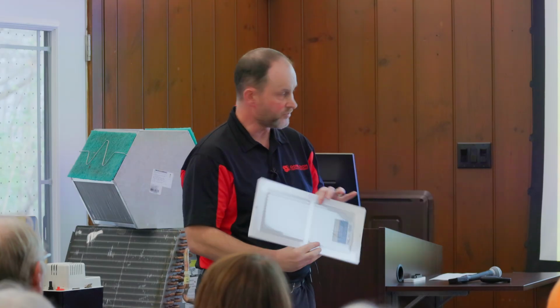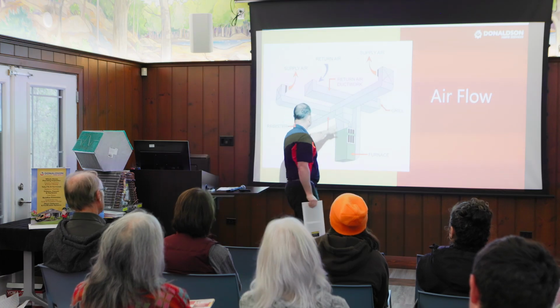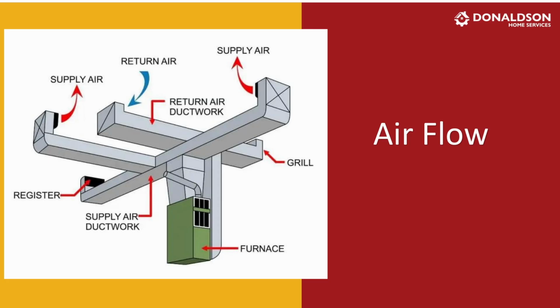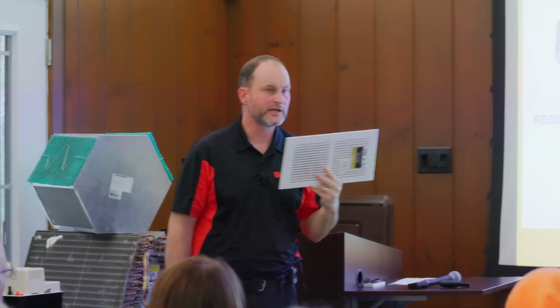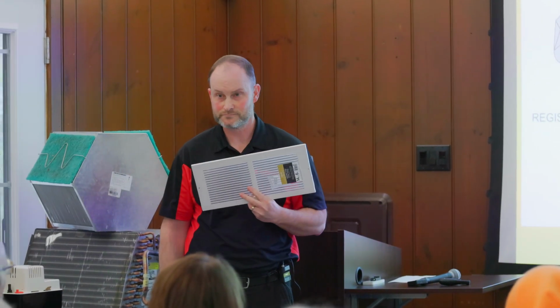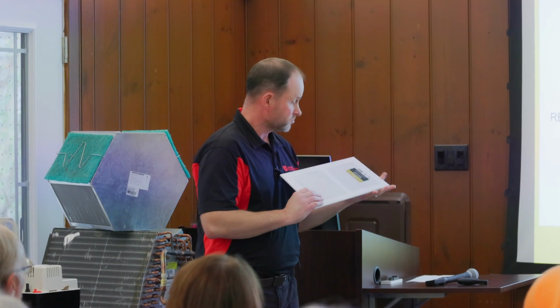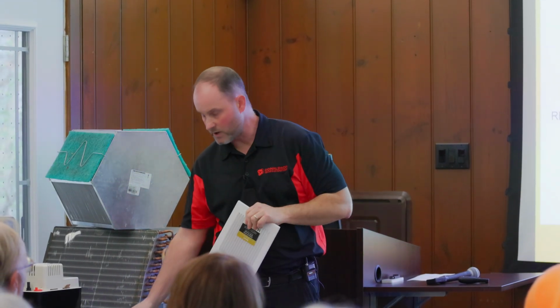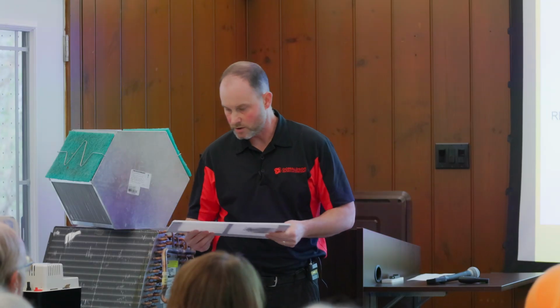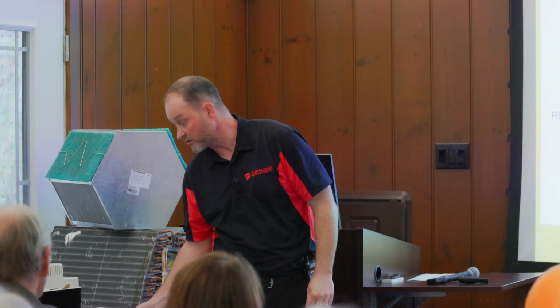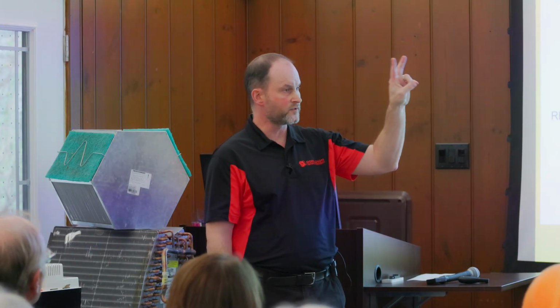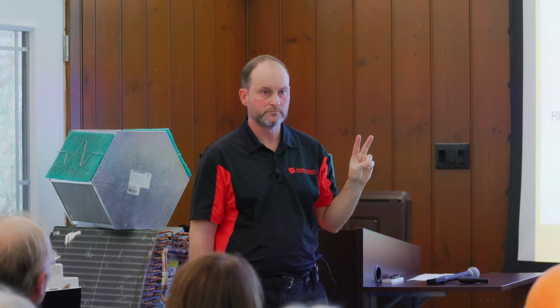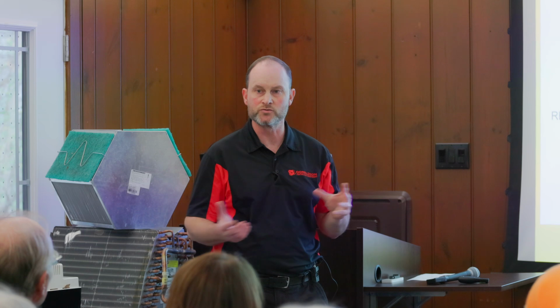Your system can only supply and push out what you're returning. So if you don't have enough return air, you're in trouble right off the hop. Return air grills are larger than supply air grills, but if you're unsure, it's worthwhile to have someone like myself come out to look at this for you. The two most common things we see are: not enough return air, and equipment not sized correctly to the home. A proper heat loss, heat gain analysis needs to be done to ensure that.